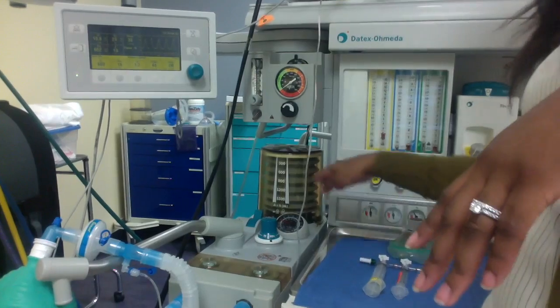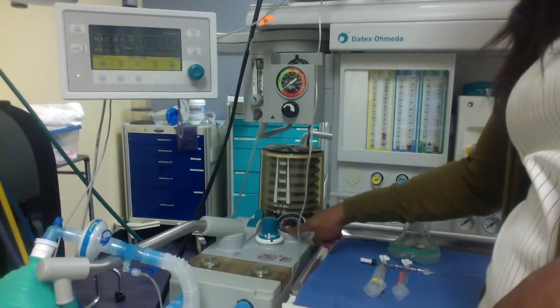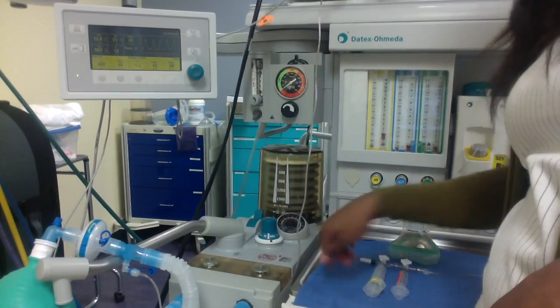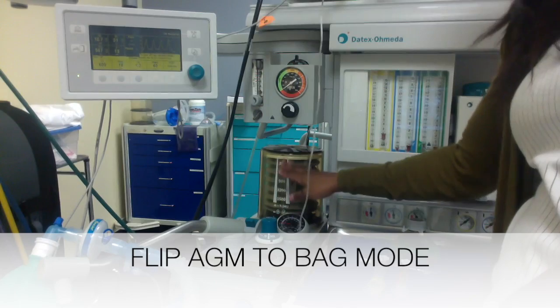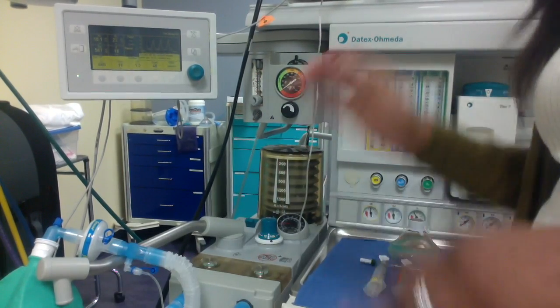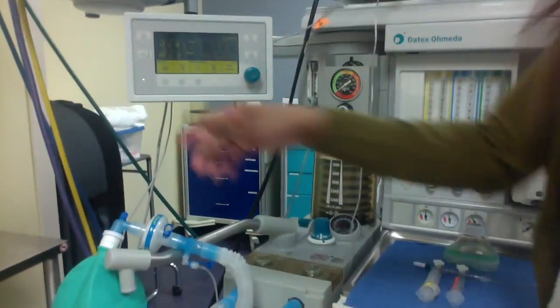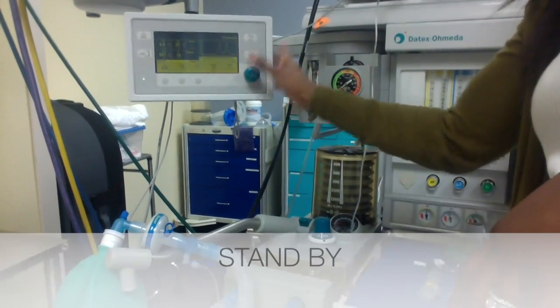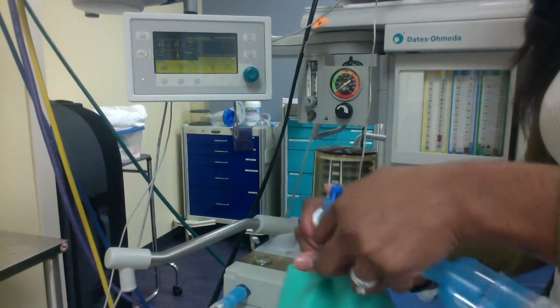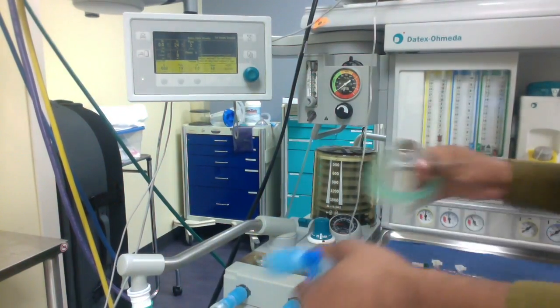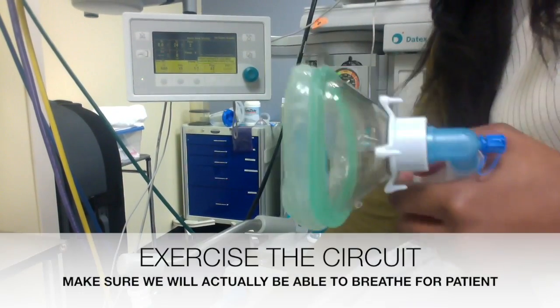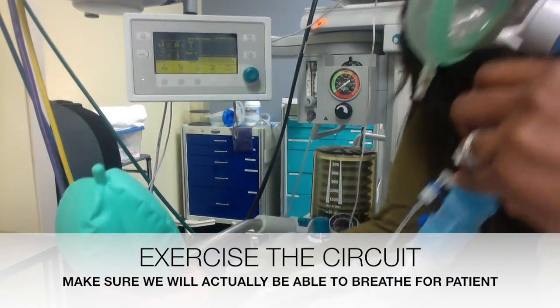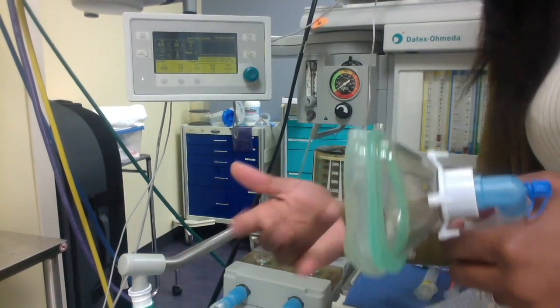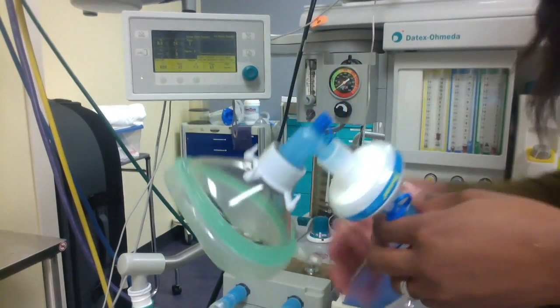So I'll be checking for the same things, that my bellows are rising and falling adequately, I'm not stacking breaths, and I'm returning close to 0 centimeters of water, and that my unidirectional valves are moving appropriately. So with that, I will stop it with my bellows filled all the way to the top, and I can do my final checkout. So what will happen is I'll put my machine on standby. So once I've done that and shut it off, I'll take my bag and hook this up, put my mouthpiece back on. I'll exercise my circuit, and I'll squeeze the bag and feel that I feel air coming out of it, and I do. So that's exercising your circuit.